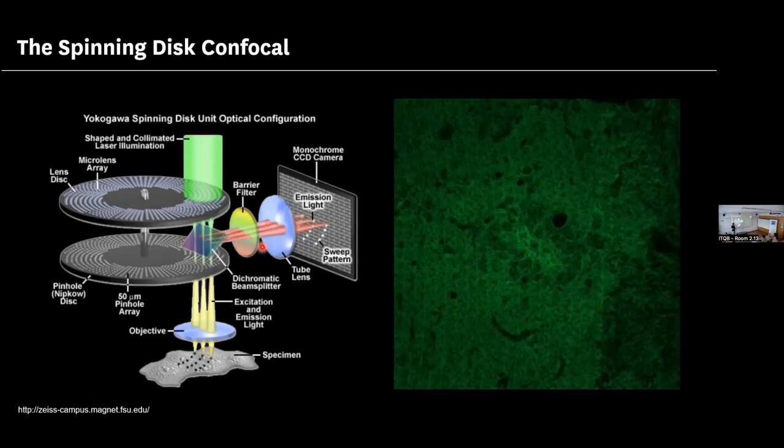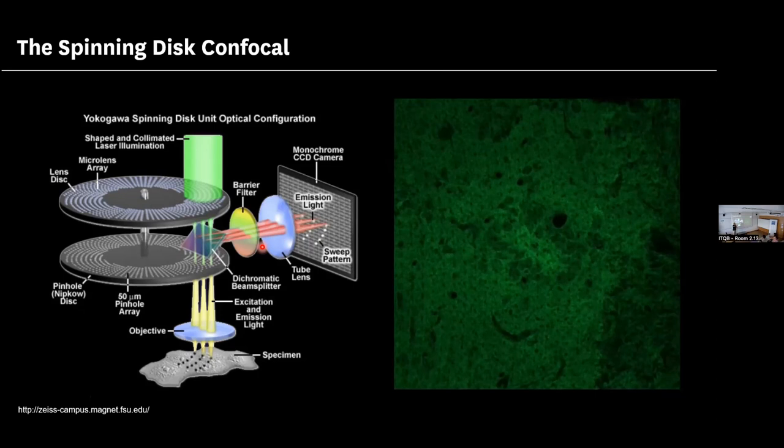This is probably due to the photophysics of the fluorophores, because on the point scanner you are exciting each single point with a lot of laser light, capturing light from that point, point by point by point. On a spinning disk, each point is being intermittently excited. As the disk rotates: on, off, on, off, on, off, on, off.